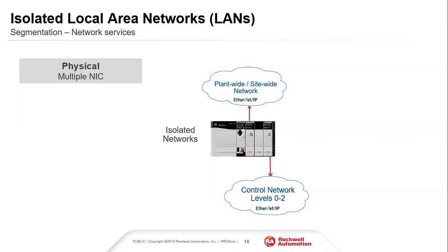The other thing that you can also look at is one of these cards may be dedicated to, let's say, Modbus. We were talking about HMS earlier. If you get an HMS, ProSoft, or Molex gateway card that goes in the chassis, you're already doing that segregation on the third-party equipment. On the top end side, the Rockwell controller doesn't care. It just brings in the data points directly into the processor, and it can be collecting data from 3, 4 different Ethernet adapters.